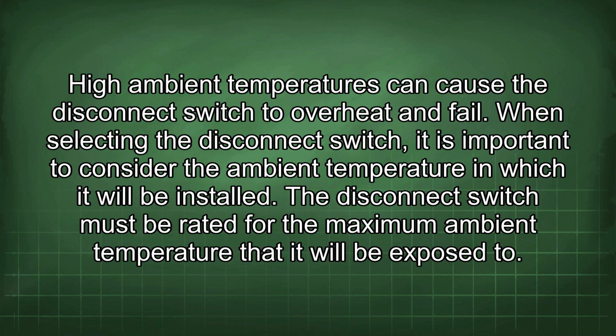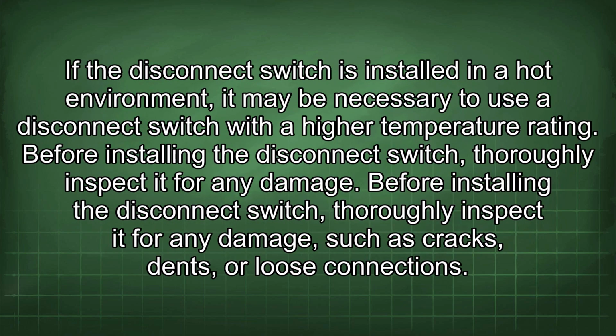The disconnect switch must be rated for the maximum ambient temperature that it will be exposed to. If the disconnect switch is installed in a hot environment, it may be necessary to use a disconnect switch with a higher temperature rating. Before installing the disconnect switch, thoroughly inspect it for any damage.